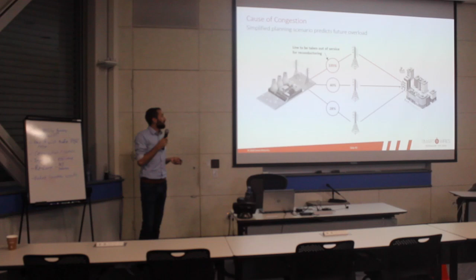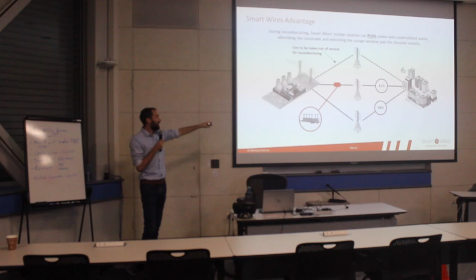Jumping back here—if we target this line, assuming a summer peak case, when you take that line out of service you'll eventually have problems on the other parallel paths, so you wouldn't be able to work on the line during this period. The great thing about our mobile solution is it's a rapidly deployable system with a temporary installation method. It can be wheeled to that line just when you want to do construction work, resolving the overload by pushing it onto the other parallel path, enabling you to take that line out of service for a longer period to complete the work.